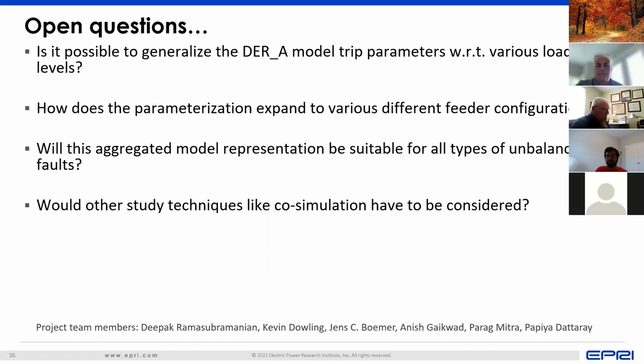Okay, cool. I wonder if I can make another observation. I chaired the revisions to 1547 and 1547.1. The three things that we had to address that made it obvious that DER standards were not finished were, one, to allow DER to provide reactive power flow; two, for the DER to be able to ride through higher voltage depressions for longer periods of time; and three, the window on frequency drop had to be widened and allowed also for ride through.